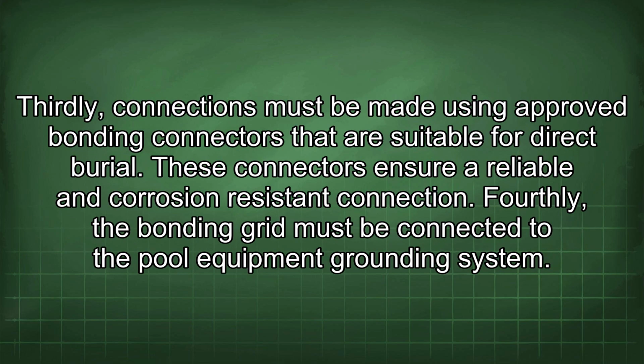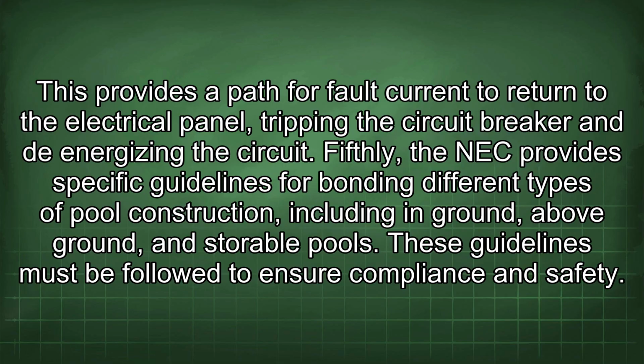Thirdly, connections must be made using approved bonding connectors that are suitable for direct burial. These connectors ensure a reliable and corrosion-resistant connection. Fourthly, the bonding grid must be connected to the pool equipment grounding system. This provides a path for fault current to return to the electrical panel, tripping the circuit breaker and de-energizing the circuit. Fifthly, the NEC provides specific guidelines for bonding different types of pool construction, including in-ground, above-ground, and storable pools. These guidelines must be followed to ensure compliance and safety.